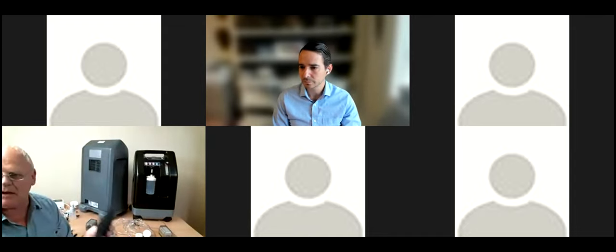These do need cleaning very regularly, and washing them with water and making sure they're dry before you put them back is the right way to go. If you do have a spare, then that's always very useful to be able to rotate those. You should be able to see through it if you hold it up to the light. I have seen cases where people have lost the foam filter and found a piece of closed cell foam and put that in. No air goes through it, and then you're not going to get the concentrator to work properly.